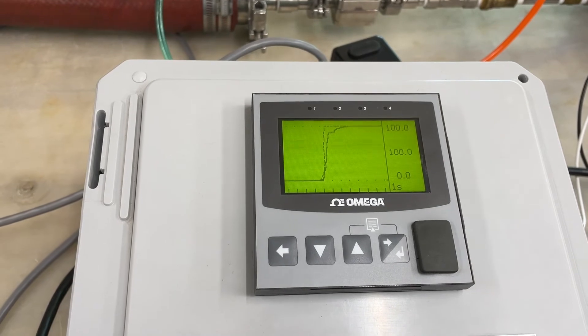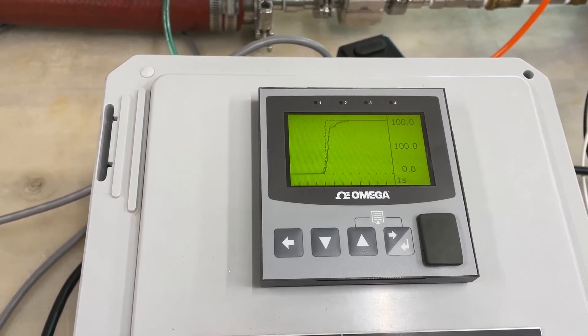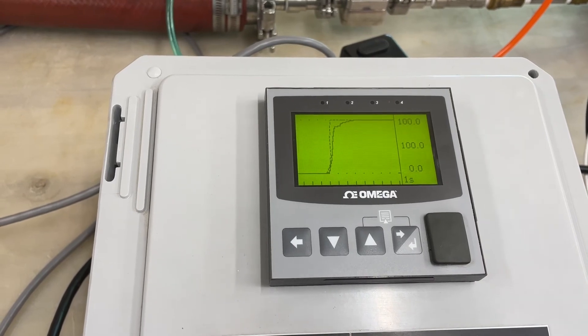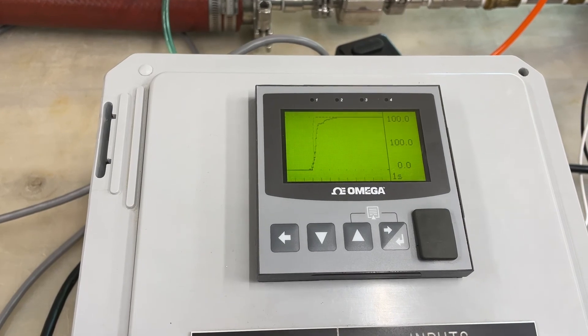Now the flow is at 100% set point or 1000 grams per minute. You can see how the PID loop adjusted the pressure on the dome to achieve the correct flow. With our Equilibar flow control valve and this PLC setup we have achieved a 100 to 1 turndown ratio.